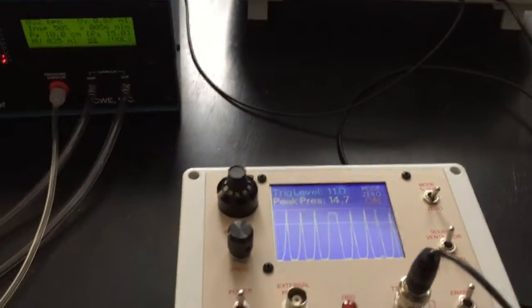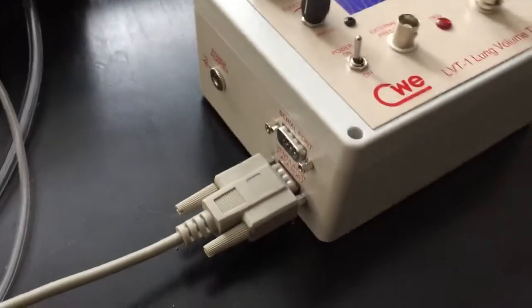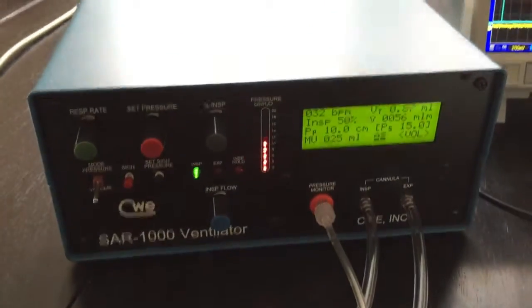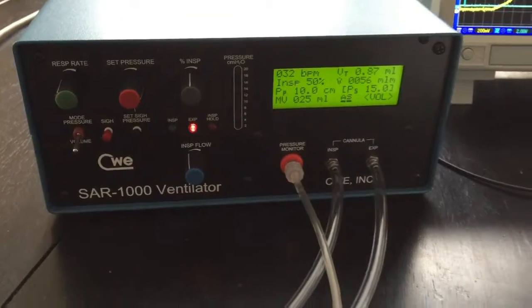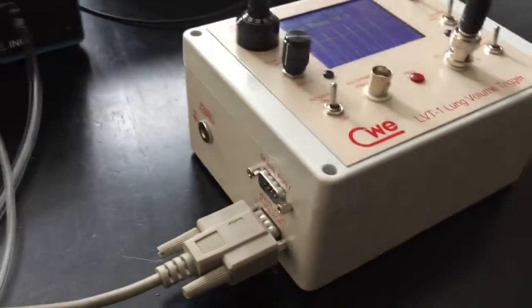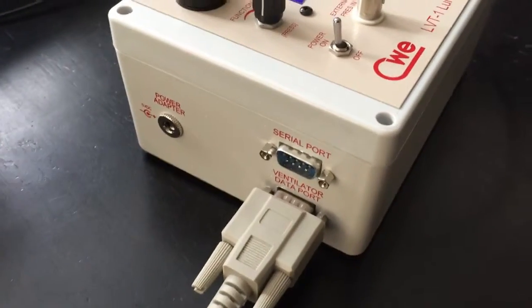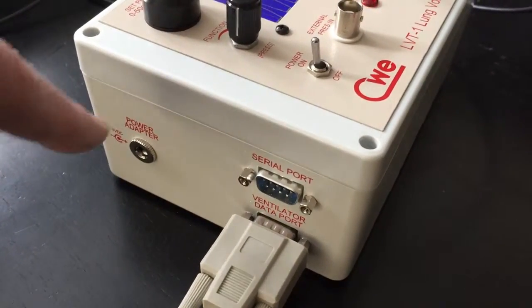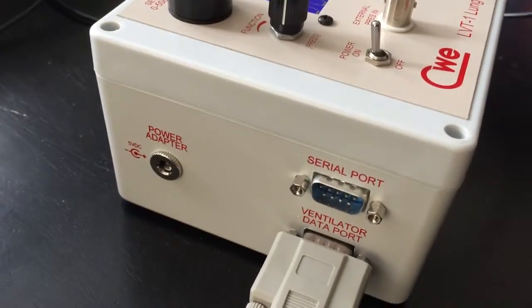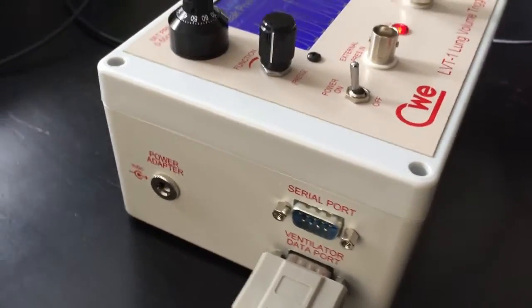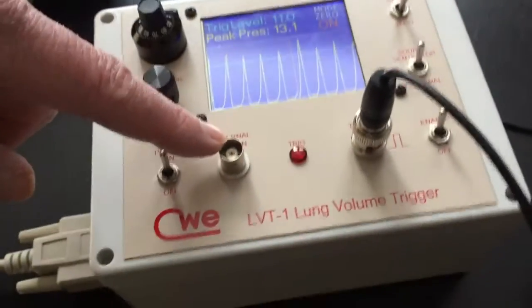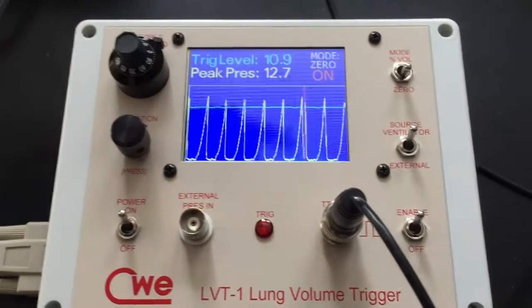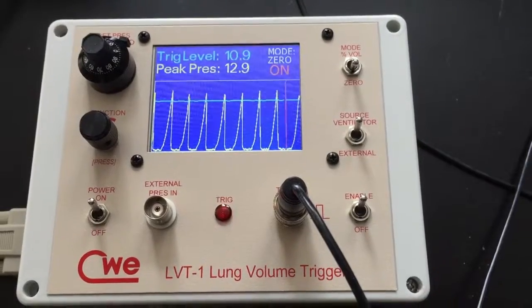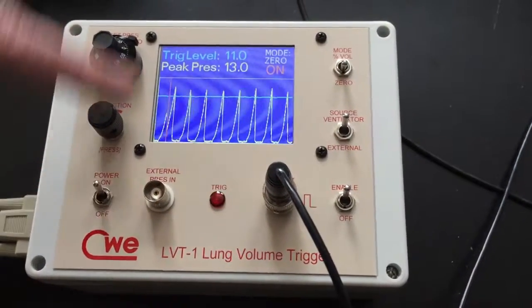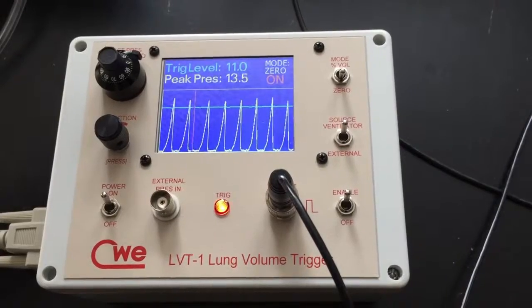And the unit connects directly to our SAR 1000 ventilator, but it can be used with any other ventilator system. Right now it's getting its power and signals by a single cable from the ventilator, but you can also use it separately. It has a provision for an external power adapter you plug in there, and then you can use the external pressure inlet here, which will connect up to any pressure signal. And as long as the scaling is correct, then all the calibrations will be correct.